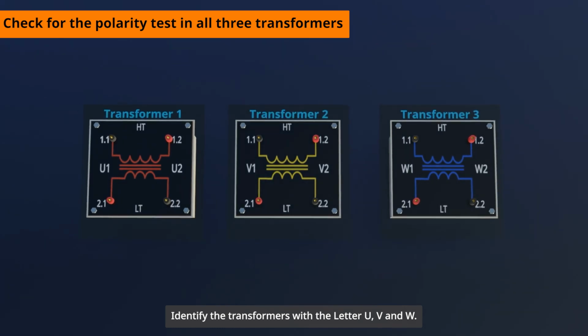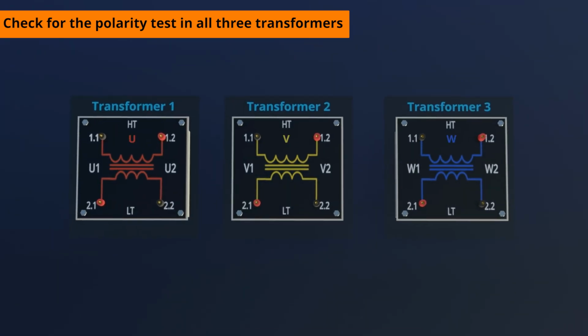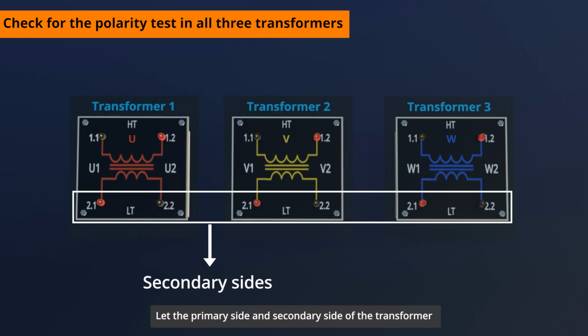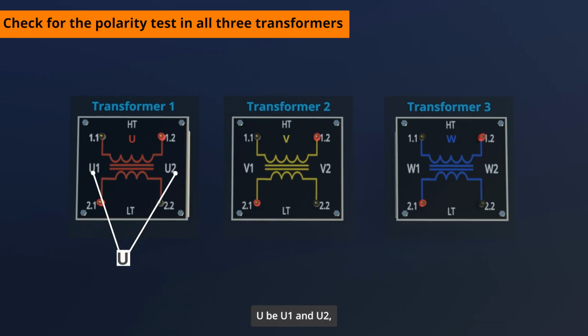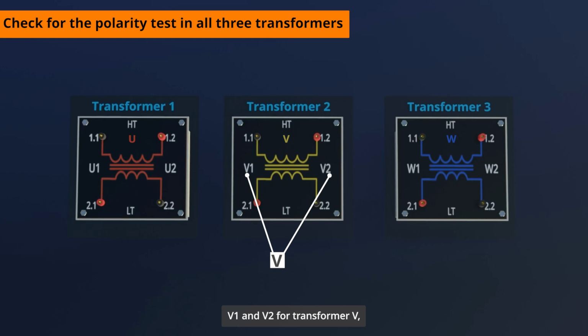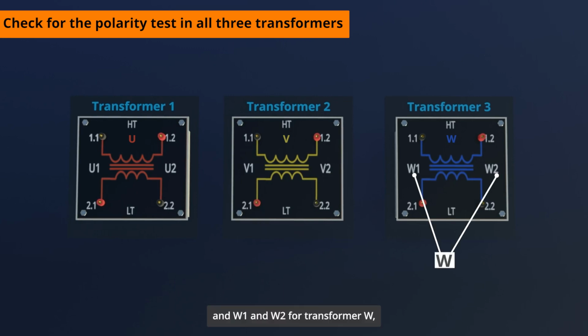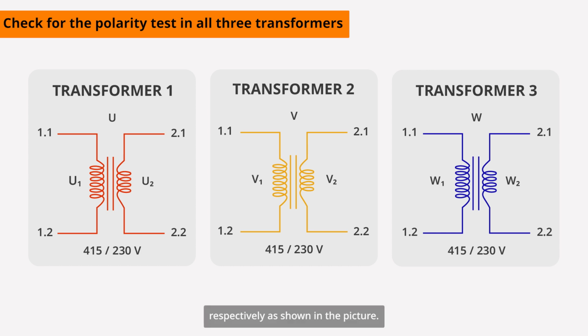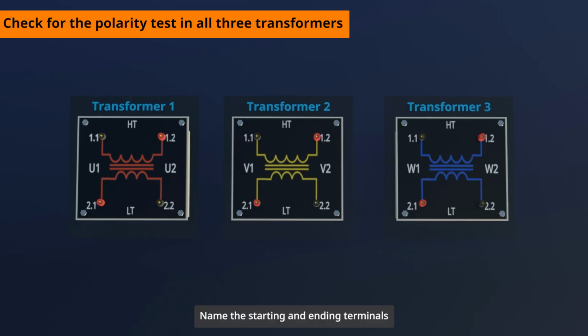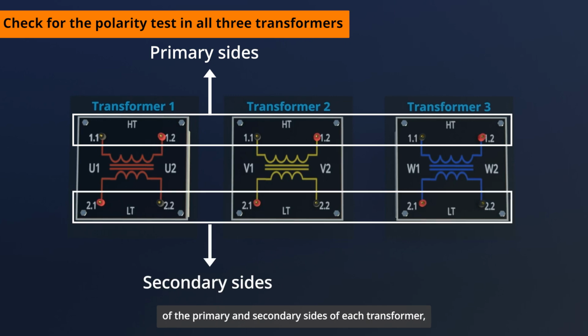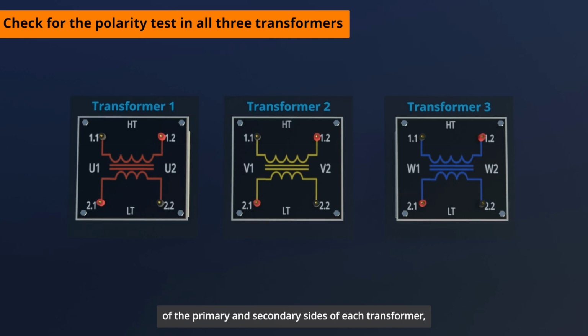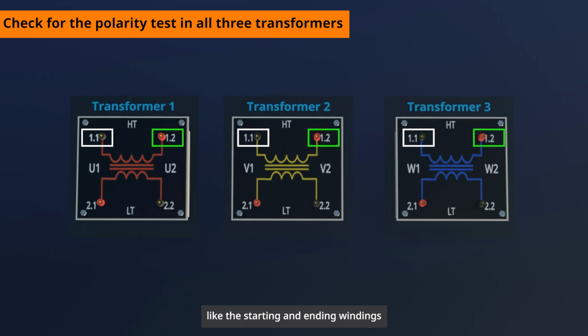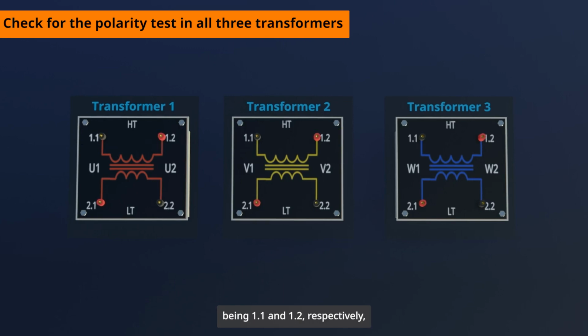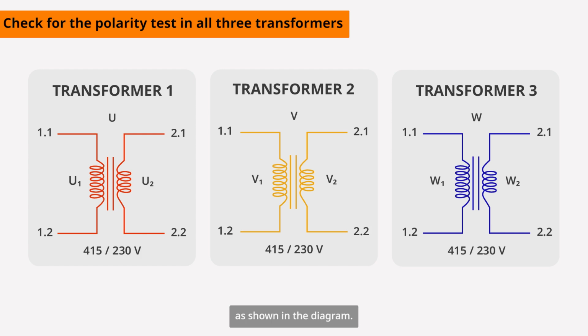Identify the transformers with letters U, V and W. Let the primary side and secondary side of transformer U be U1 and U2, V1 and V2 for transformer V, and W1 and W2 for transformer W, respectively, as shown in the picture. Name the starting and ending terminals of the primary and secondary sides of each transformer, like the starting and ending terminals of the primary windings being 1.1 and 1.2 respectively, and the starting and ending terminals of the secondary windings being 2.1 and 2.2 respectively, as shown in the diagram.